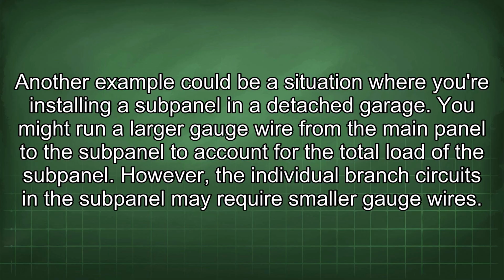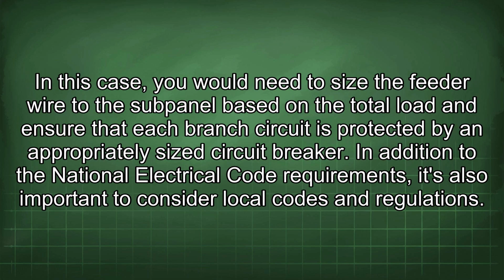Another example could be a situation where you're installing a subpanel in a detached garage. You might run a larger gauge wire from the main panel to the subpanel to account for the total load of the subpanel. However, the individual branch circuits in the subpanel may require smaller gauge wires. In this case, you would need to size the feeder wire to the subpanel based on the total load and ensure that each branch circuit is protected by an appropriately sized circuit breaker.